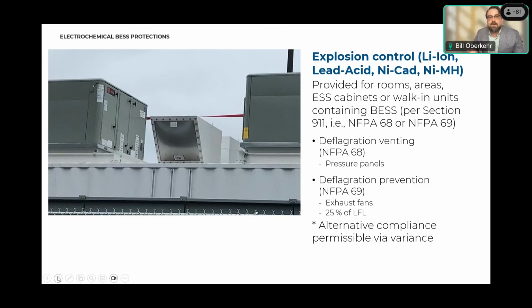Explosion prevention systems are aimed at keeping the gas buildup within the container below 25% of the lower flammable limit of the gas mixture contained. It is important to understand that not only NFPA 68 and NFPA 69 are viable options. We do check for deflagration analysis both in the UL 9540 listing and through NYSERDA's peer review to verify that the data behind other types of explosion systems that don't meet 68 or 69 does justify that that system works to contain the hazard presented. Next slide, please.